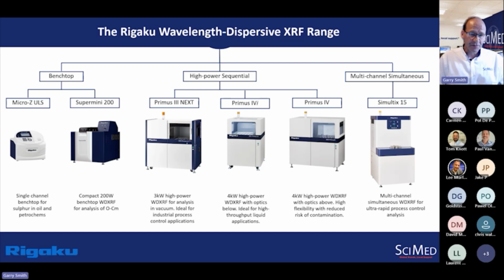The Primus 4 systems, the 4 kilowatt systems, add benefits in terms of improved sensitivity, and also additional optional features such as sample mapping and small spot functionality, as well as the ability to purge the atmosphere with helium and measure with a helium purge atmosphere for liquid analysis. So the Primus 4i is ideal for high throughput liquid applications. Also has a very small footprint, one of the smallest footprints of any 4 kilowatt spectrometer on the market.